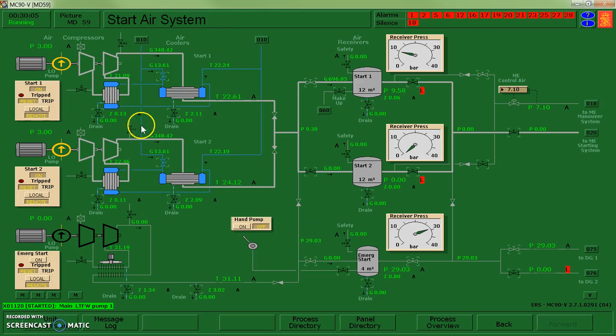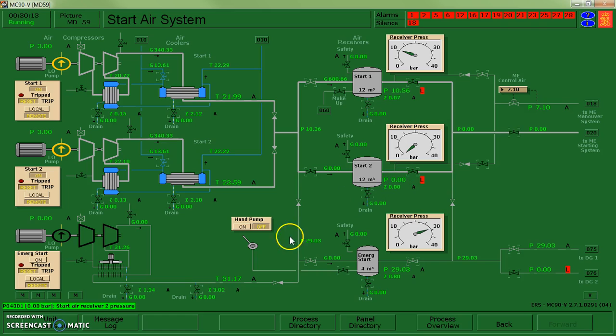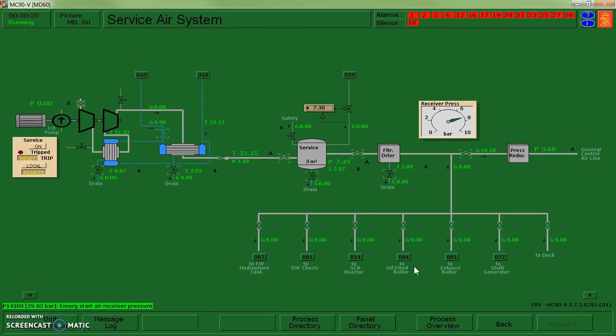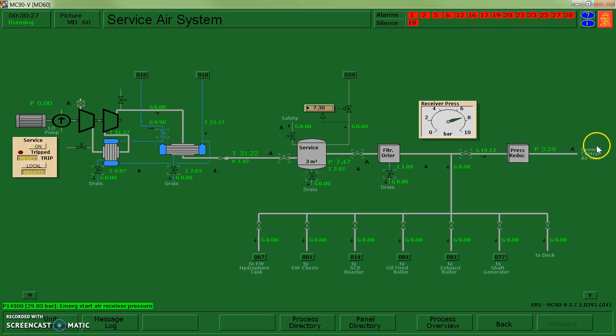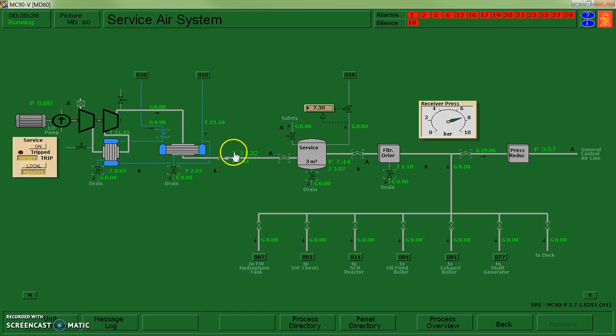My air compressors: I have my two main start air compressors that are starting to fill up this tank and eventually I'll fill up the other tank. I have my emergency compressor that's now off because it has filled up the emergency start. My service air system is charged and providing air pressure to my control airline. My service air compressor is off right now but it's remote controlled, so the control system has decided that it's okay how it's sitting and it is off.